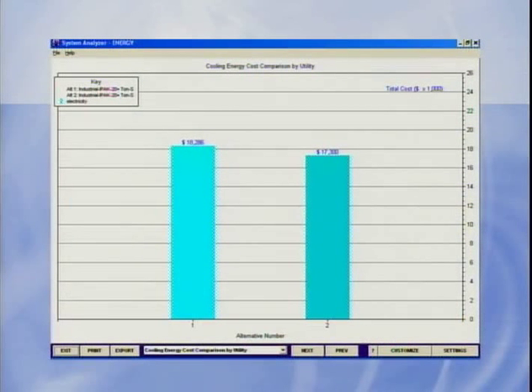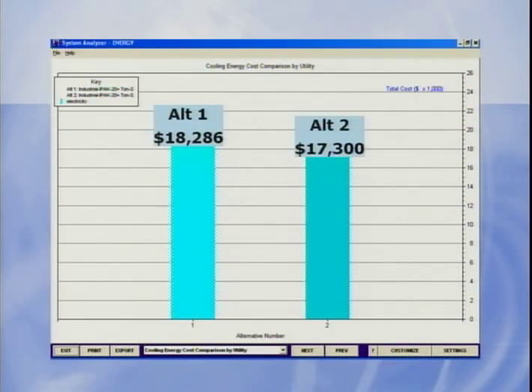Using the energy efficiencies of the standard and high efficiency units at identical operating conditions, we can generate an HVAC energy cost comparison. We can see by comparing the two systems that the higher efficiency rooftop system yields an energy savings of approximately $1,000 the first year of service. Some would consider this savings insignificant compared to the additional first cost of the optional high efficiency components. However, over a 20-year system life, this represents a simple savings of around $20,000. When combined with other energy saving strategies that we will address later in this broadcast, the investment in high efficiency options becomes much more attractive.